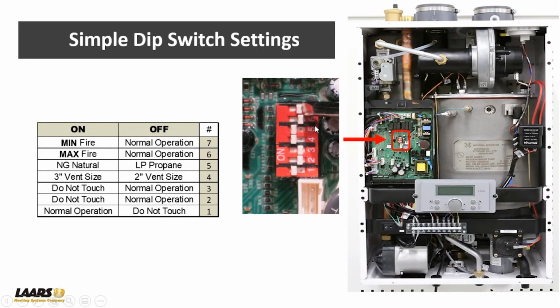We have a series of dip switches here, and we'll talk about high fire and low fire, but example here, dip switch 4. Do you have a 2-inch vent you're using or a 3-inch vent? So the collars up top are for 3-inch vent, and you can reduce that to 2-inch if you've got a little short run. So dip switch 4, you would very simply put to the right-hand position for a 2-inch vent. Dip switch 5, natural gas or propane. Again, they all ship natural gas. And as you'll look, you'll see dip switch 5 in the left-hand position for natural gas. Propane, the orifice comes with the boiler. You install a new orifice and throw dip switch 5 to the right-hand position. That's it. Now you're converted to propane.